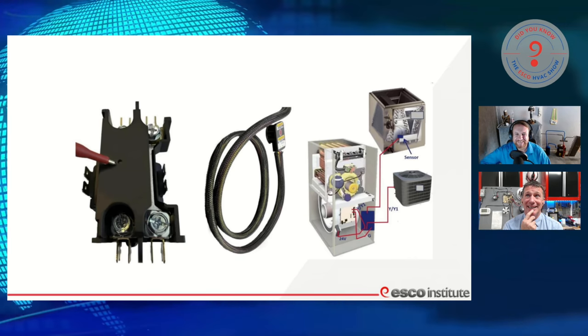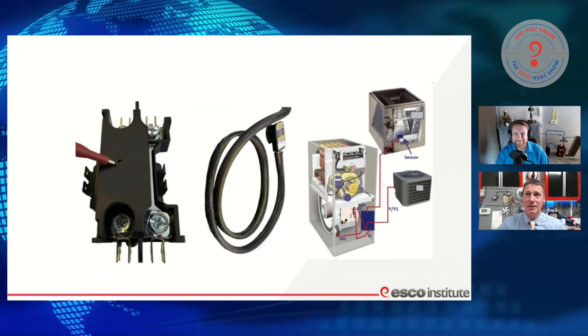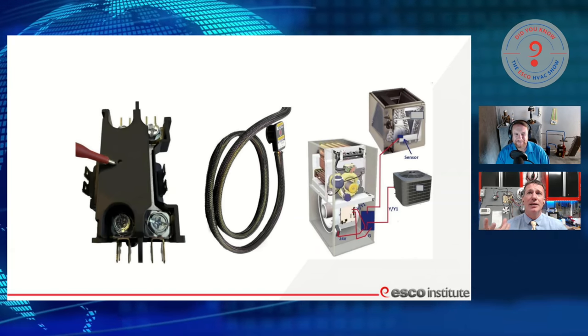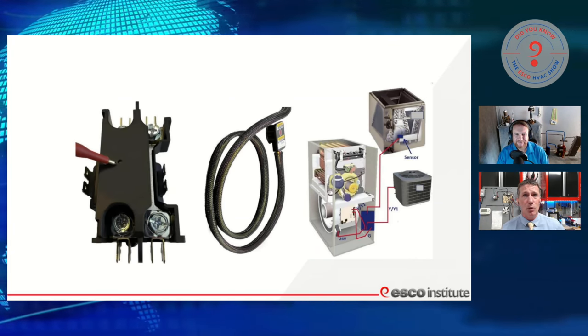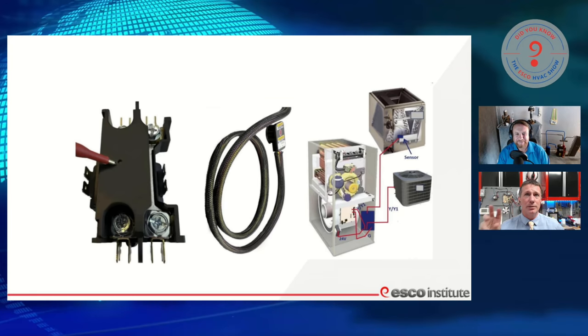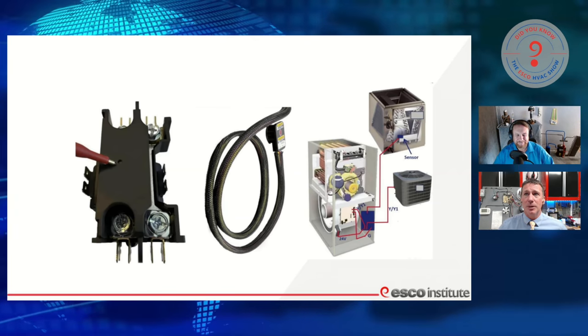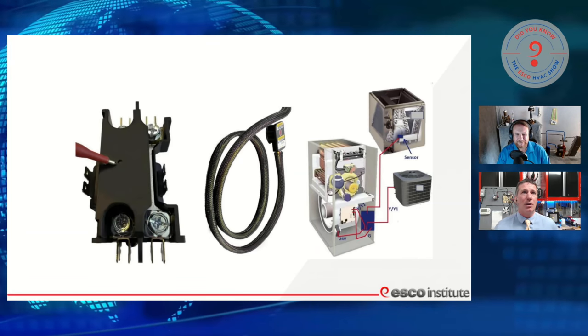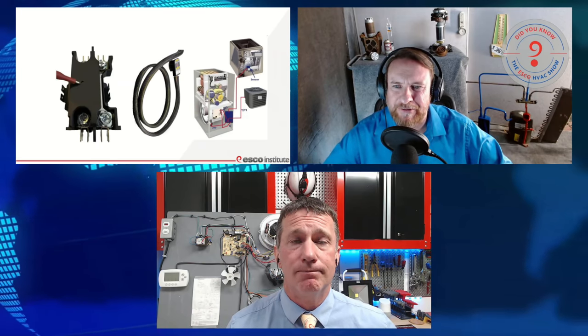So if we think about those points, how can we reduce that potential ignition? Well, we actually did try a couple of decades ago — we started enclosing the plugs that are on our compressors. So many of the things we're going to see, we're already introduced to. They just haven't been accepted as normal practices. We're going to see compressor terminals that are more concealed, contactors that are more concealed, motors and compressors with less potential for ignition. We're going to see a lot more ECM motors — and that's just because of energy efficiency anyway. Now we have an additional opportunity to start moving into components that have less ignition sources, just out of an abundance of caution.